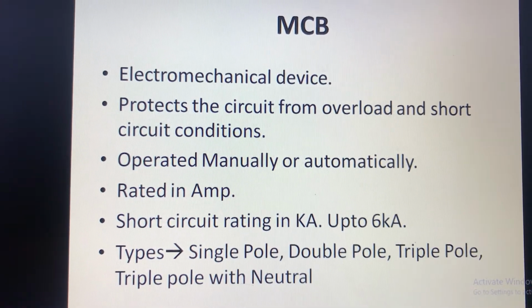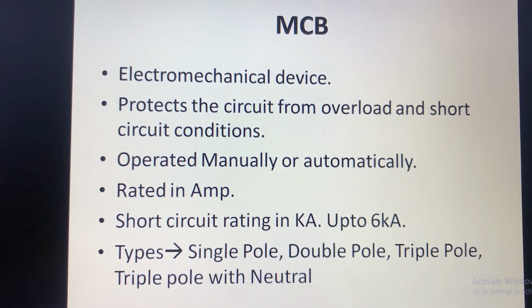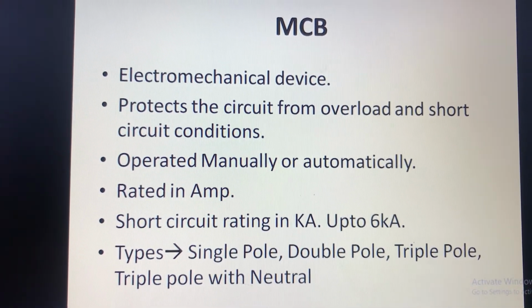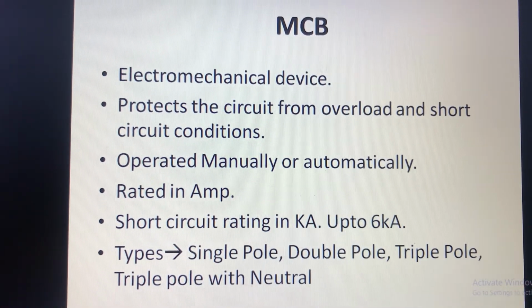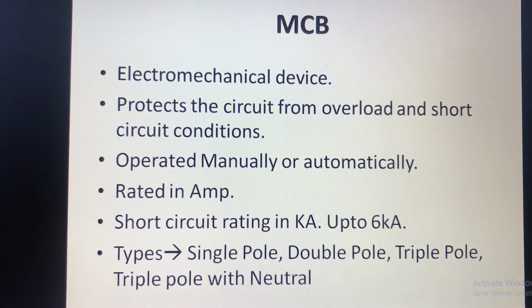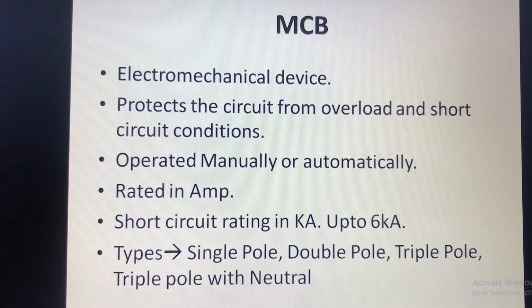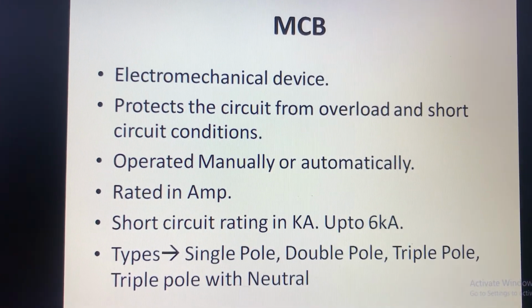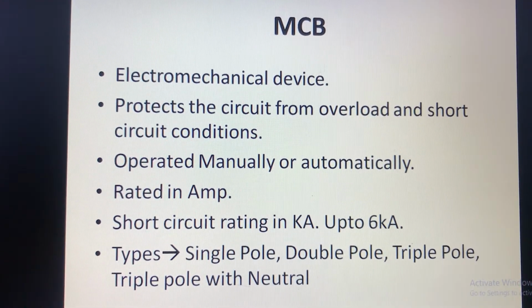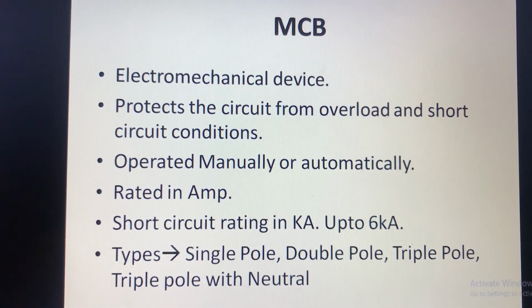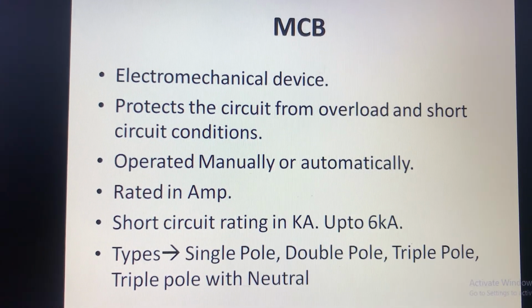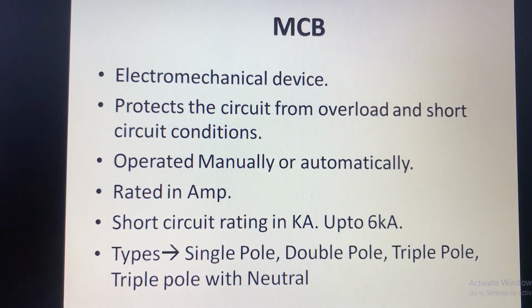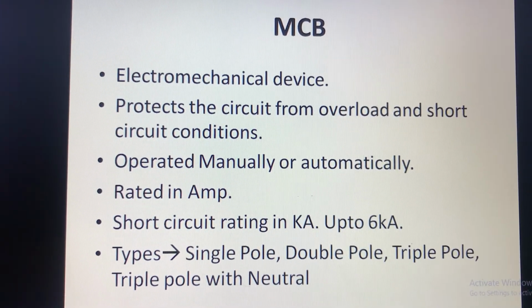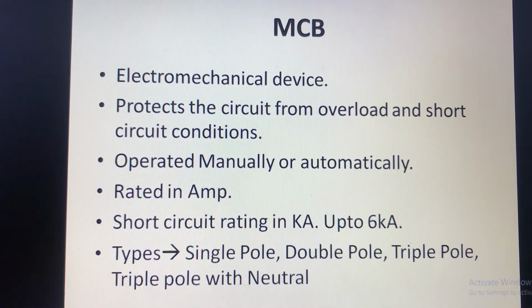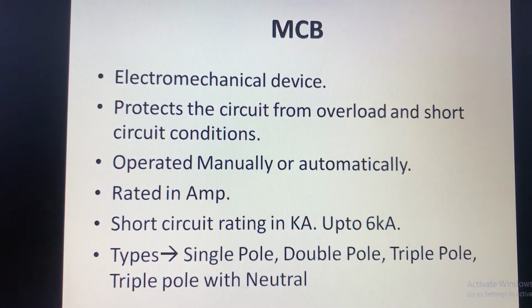So standard rating is 6 amperes for lighting circuits, like 10 ampere for large lighting circuits and 32 ampere for power circuits, and so on. It goes up to 100 amperes. Its short circuit rating is in kiloamperes. Short circuit rating means short circuit current up to which MCB provides the protection without damaging itself. So it could be up to 6 kiloamperes. So this is an MCB we are using in domestic purposes.